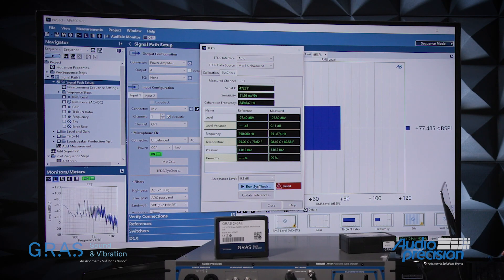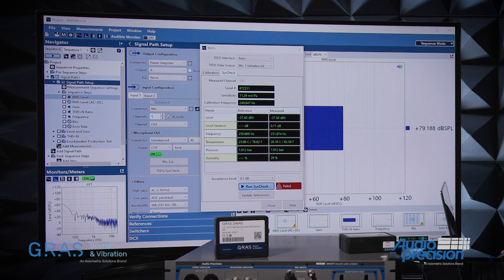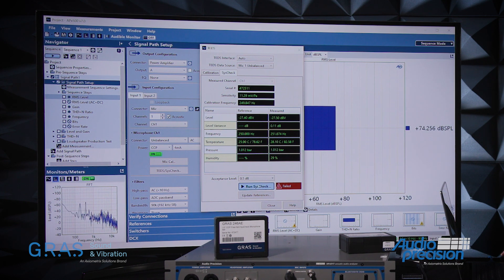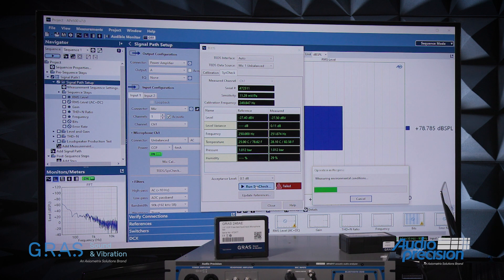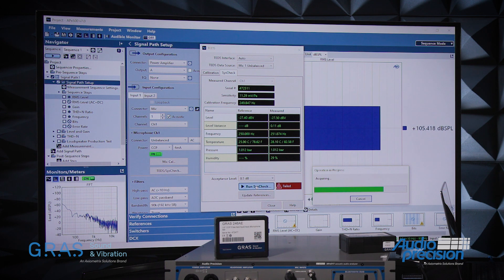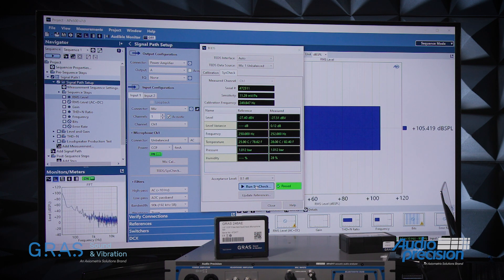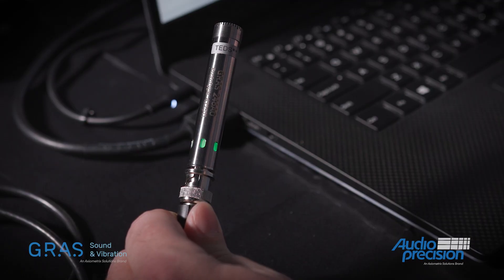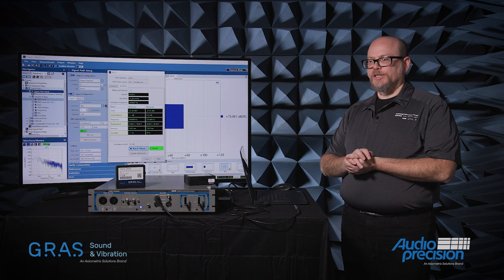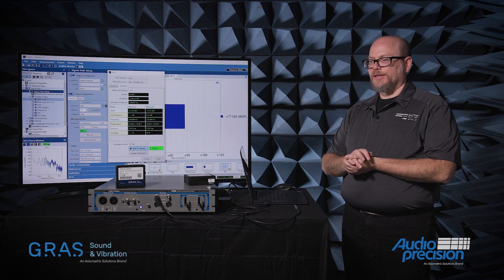Perhaps in this measurement setup I'm prepared to accept a little bit higher deviation, so I'll set my threshold to be 0.5 dB. I can run SysCheck again, and now it has calculated that this microphone is in fact operating within 0.5 dB of its design, or last calibrated, sensitivity.